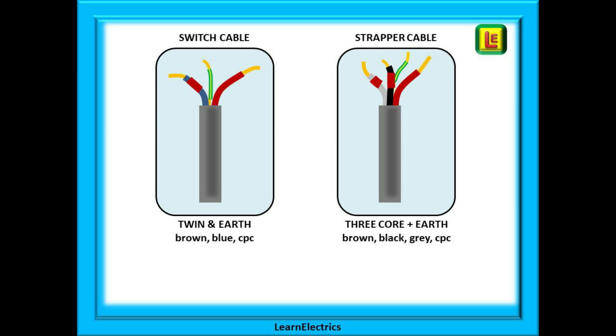We will build up the circuit in stages and then look at current flow through the circuit. The switch cable is often standard twin and earth cable. The blue is not used as a neutral. It will at some point carry 230 volts and should be marked with brown sleeving at both ends. The strapper cable is 3 core plus earth: brown, black, gray, and all three colors will carry 230 volts, so the black and gray should also be sleeved in brown. On the drawings that follow we have left off the CPC or earth and also the brown sleeving for clarity.